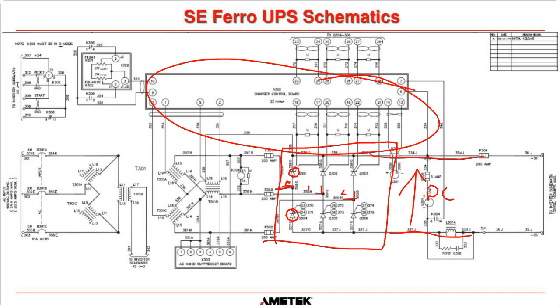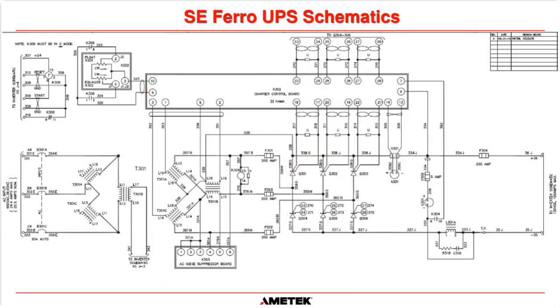Obviously, we have this control board up here that's doing all the clever work. And on a Ferro system, the older systems, that is actually an analog board, so there's no processor on this charge control board. But that sends all the signals to the SCRs. If you look here, these cables 1, 2, and 3 are monitoring the secondary of this transformer because we have to know when to turn these SCRs on. So that's us looking at the sine wave that's coming in to our system, and we can phase our SCRs on based on this voltage going into the control board. So it's very important that the voltage is correct going into that control board.